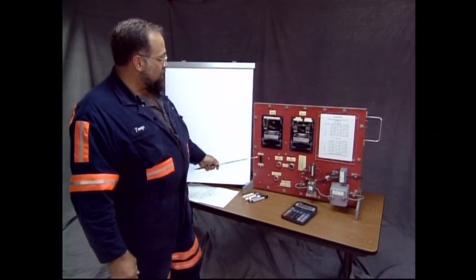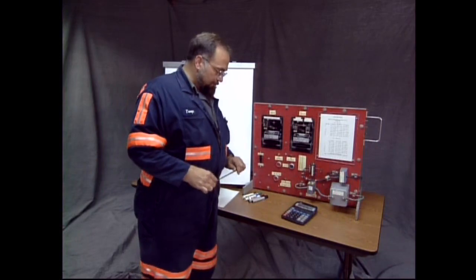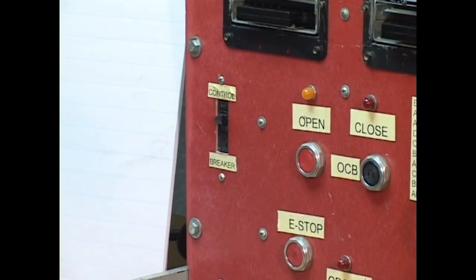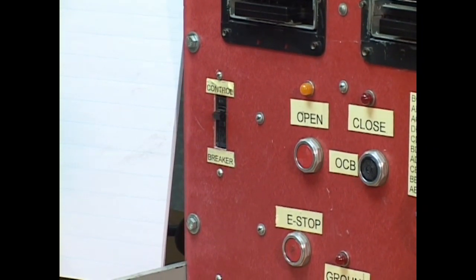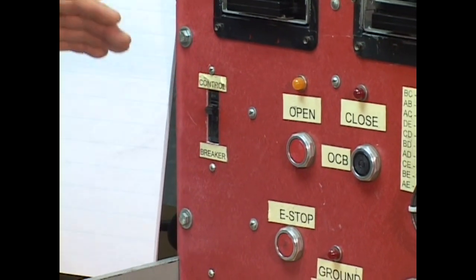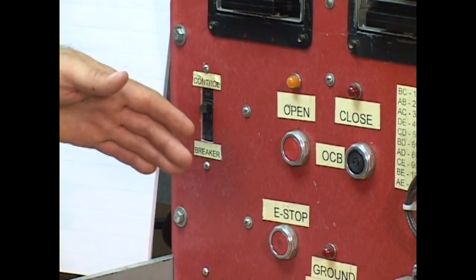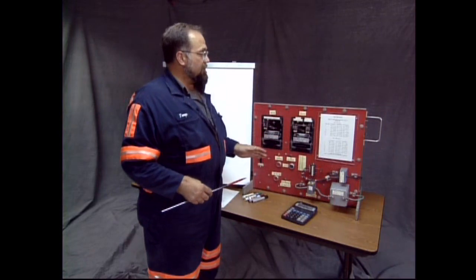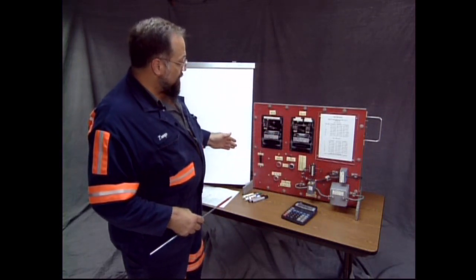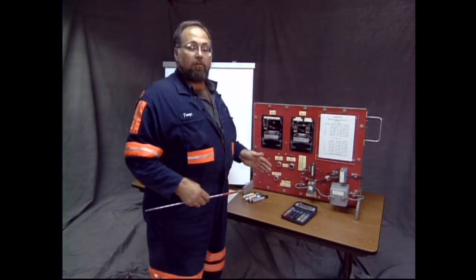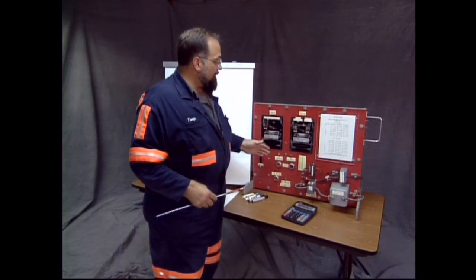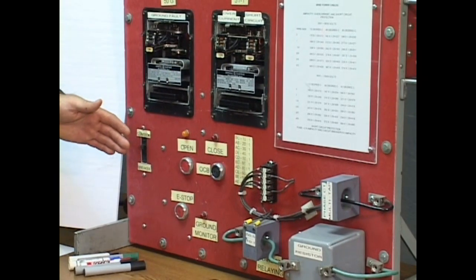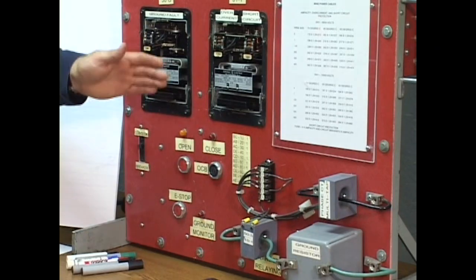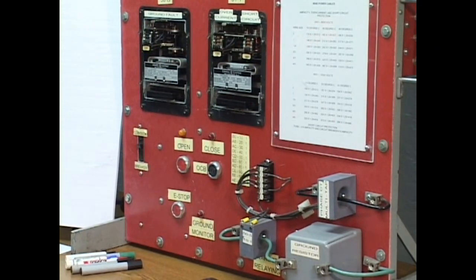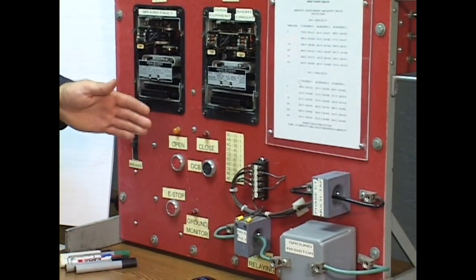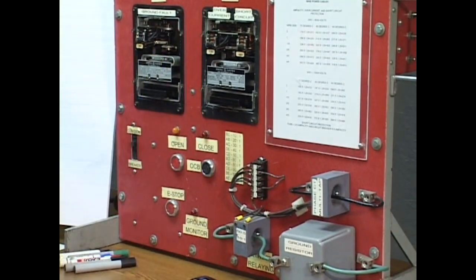And we have a control breaker. Now, the control breaker has nothing to do with the high voltage circuit per se underground. It's to protect the device, to protect the wiring of these relays. You probably have a 20 amp control breaker that will operate the relays, it will supply the control power for the relays, and its only protection is for the wiring on the controls. It has nothing to do with the protection of the high voltage cable.